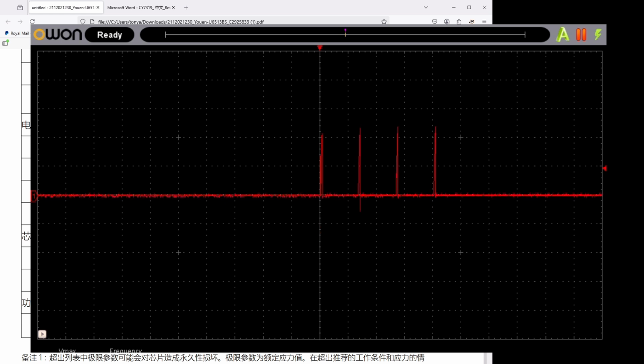So that's fairly conclusive that there's an overcurrent situation somewhere—either in the rectifier, since there's not much on the secondary side, or it could be the transformer. Don't forget, you might have shorted turns on the transformer or a burnt out winding. But having said that, it probably isn't that. But who knows what it is.